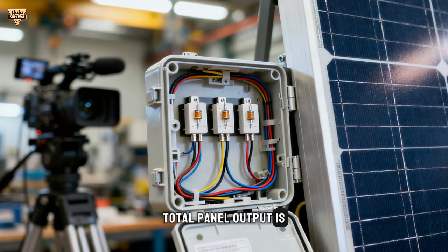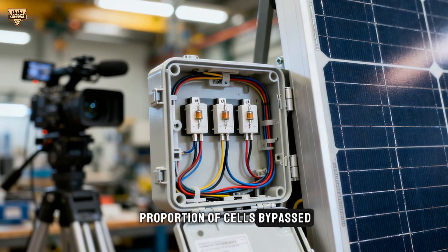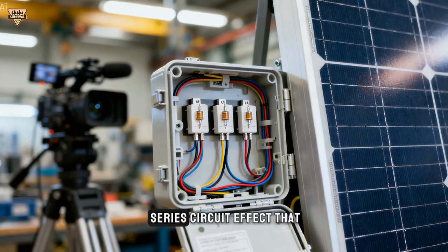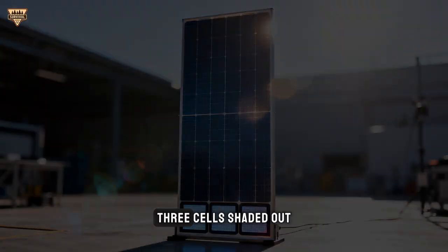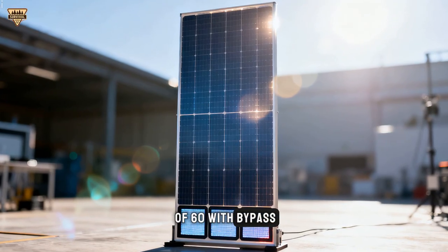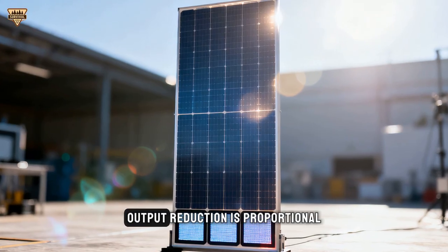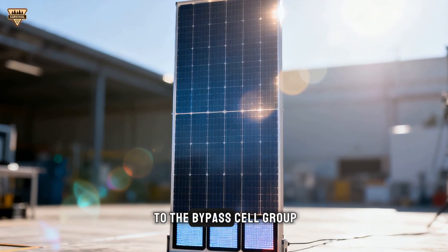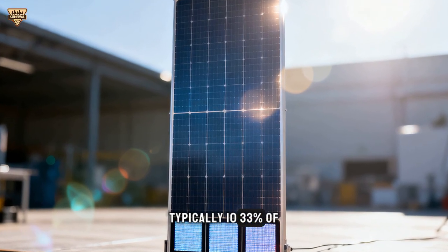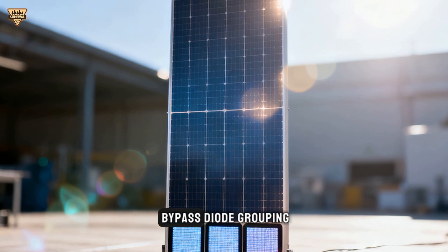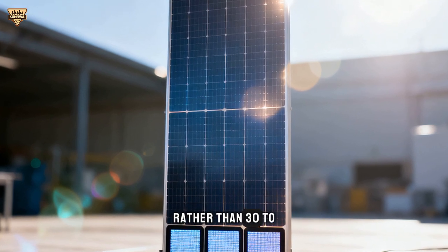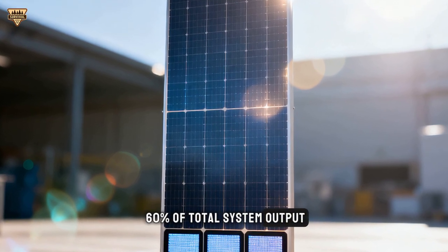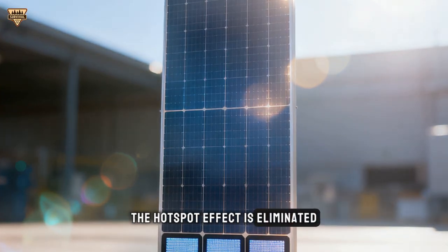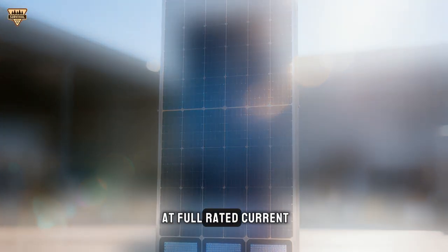Total panel output is reduced only by the proportion of cells bypassed, not by the cascading series circuit effect that would otherwise occur. 3 cells shaded out of 60 with bypass diodes properly installed. Output reduction is proportional to the bypassed cell group, typically 10-33% of one panel depending on bypass diode grouping, rather than 30 to 60% of total system output. The hotspot effect is eliminated. The unshaded cells produce at full rated current.